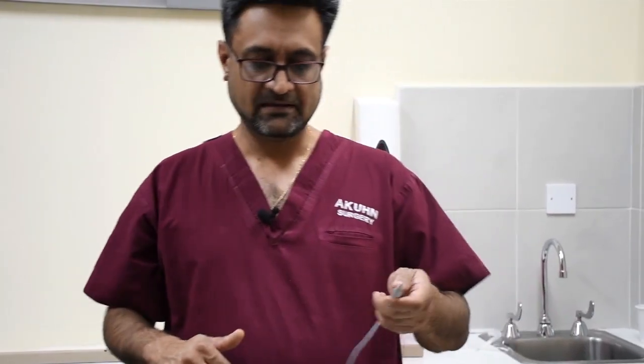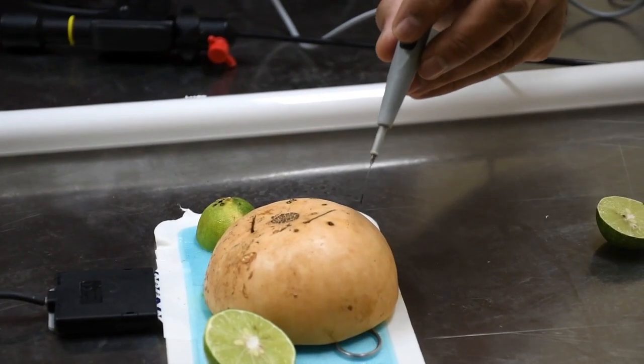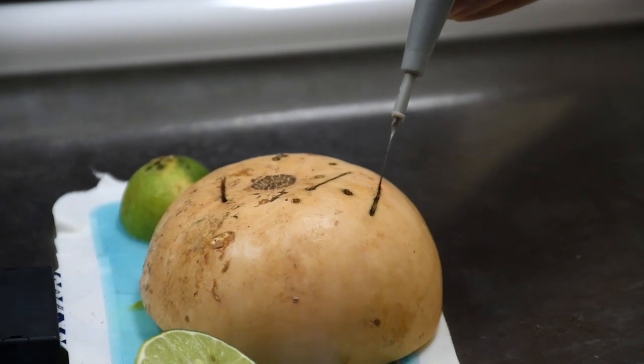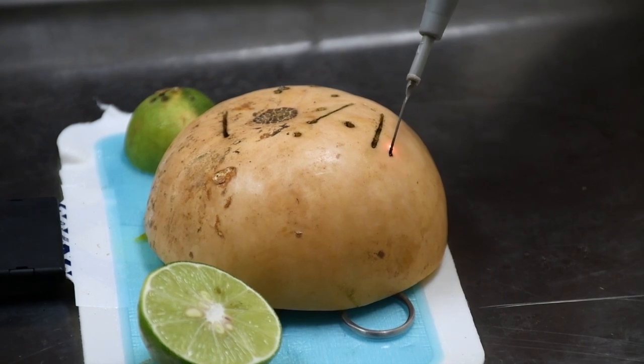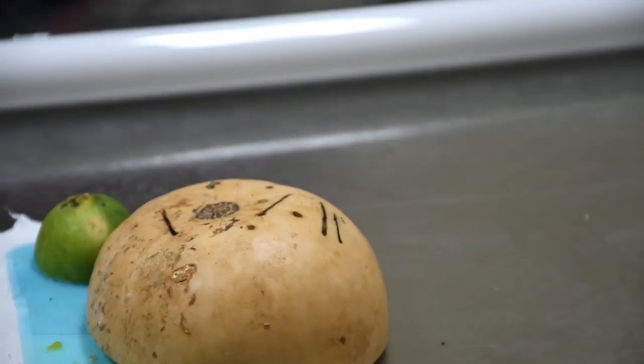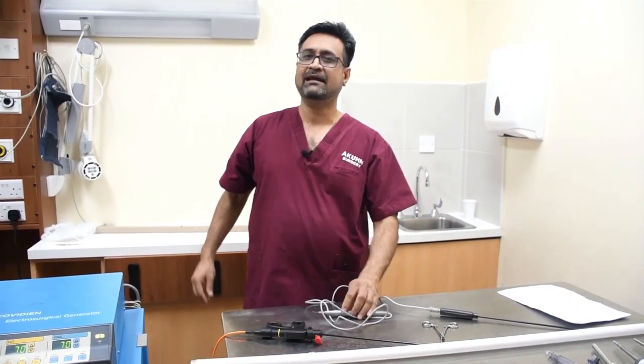Number two, what I was doing with the different surfaces, if you see before I remove this, you can see this is now cut. There is what is called the non-contact. So for cutting, if you want to cut a tissue, you activate, go close and make a cut. So it makes a cut like a fine knife. When you do the same with coag, it is very high, remember? So you're going to activate it and you're going to still cut. But what is the difference between these two cuts? The difference would be in the damage to the surrounding tissues. So if you use the cutting mode, it will have less damage to the surrounding tissues because it's low. Secondly, it will not cause too much damage.